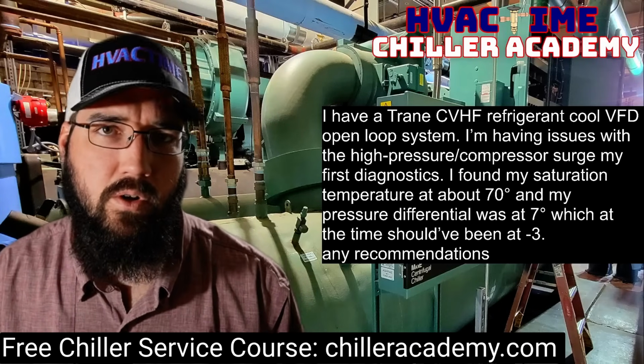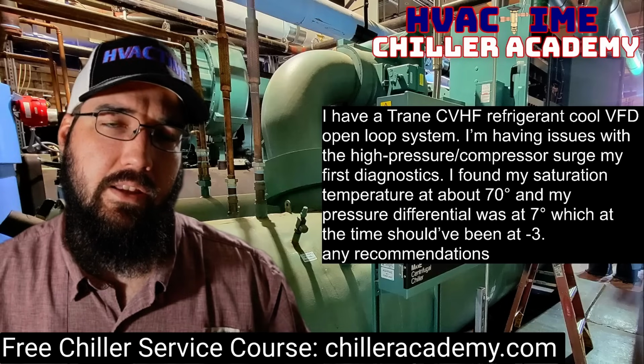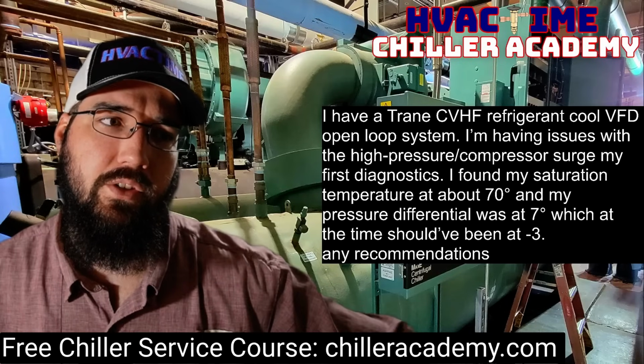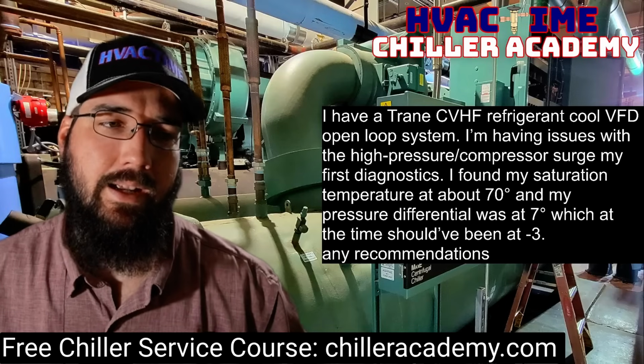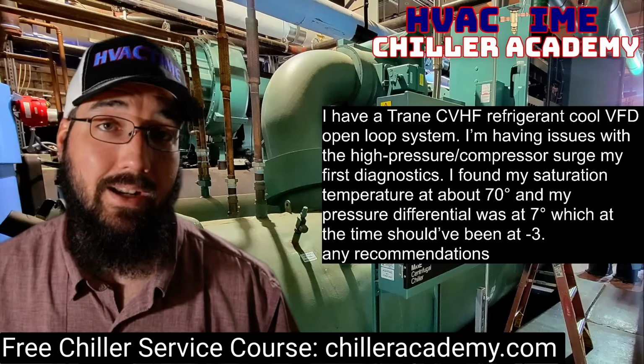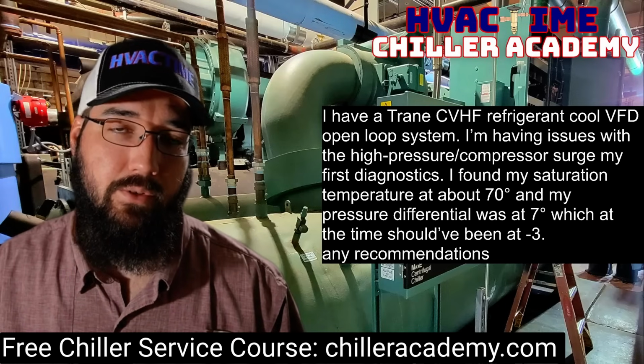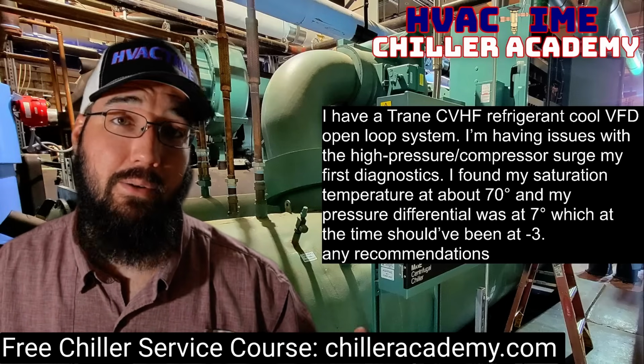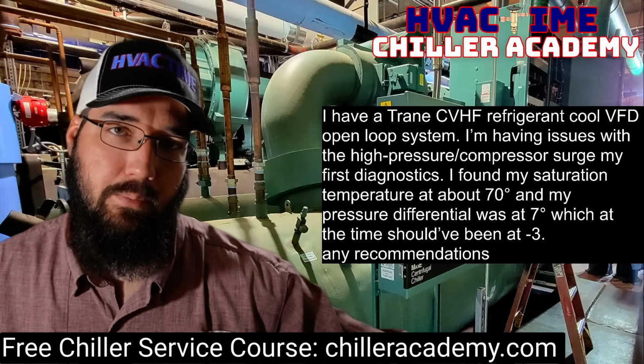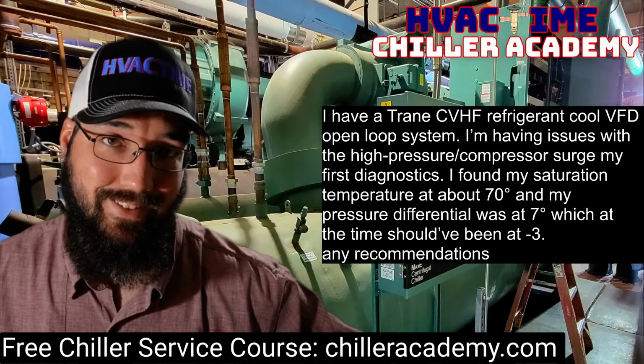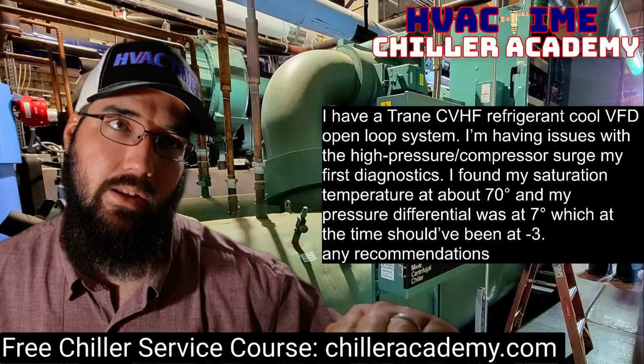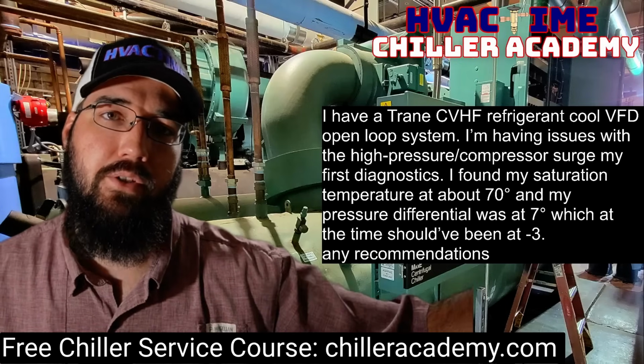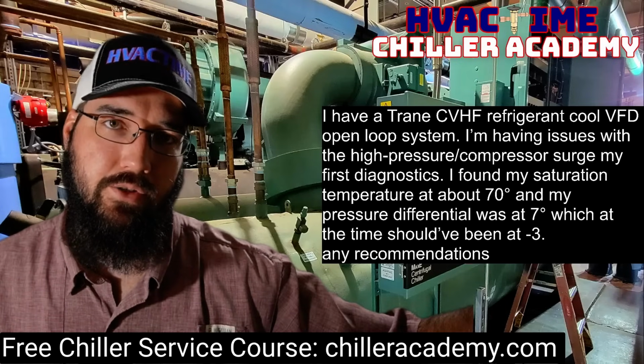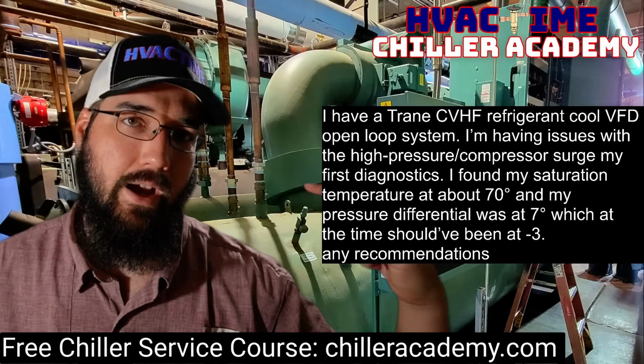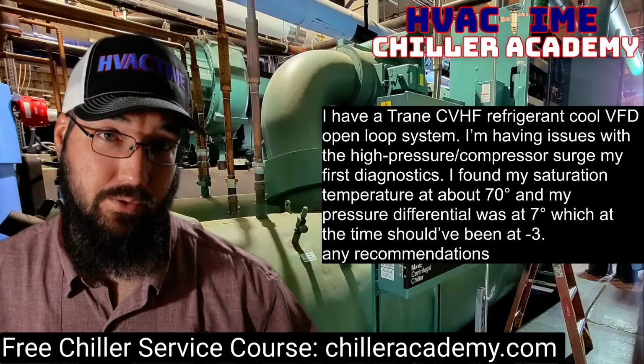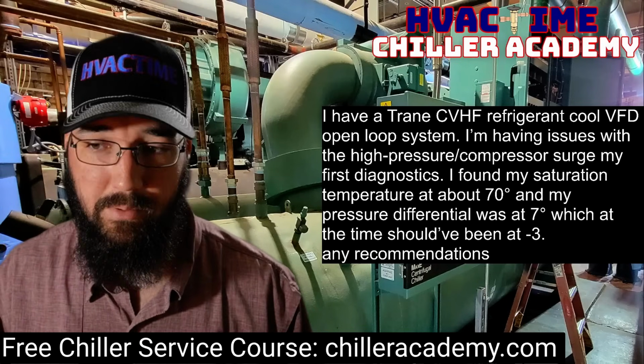I care way more about what is my DP in that circumstance than what speed my pump is being allowed to run at, and does it need to be a variable speed or not? Honestly, if I'm dealing with a surge condition in the first place like that, I would much rather keep the pump in hand so that it is consistent, because I don't want the pump trying to vary and modulate to then be another factor that I'm having to calculate into my troubleshooting. It just becomes far more complicated at that point.